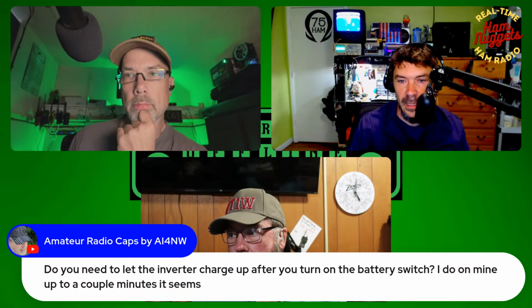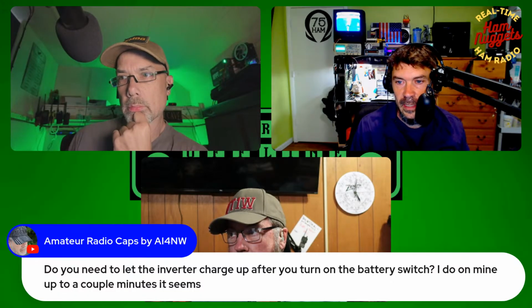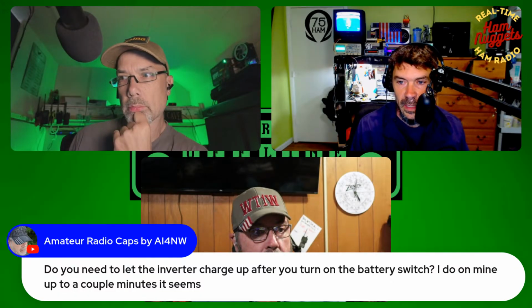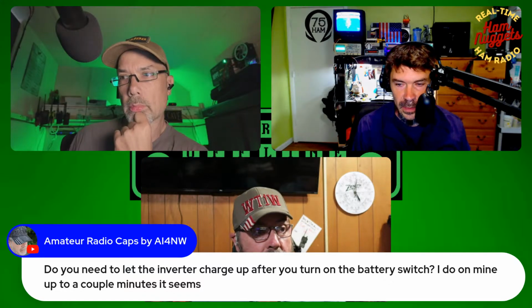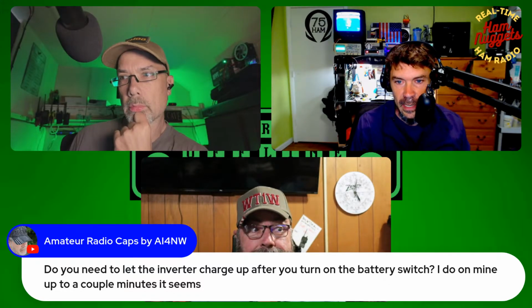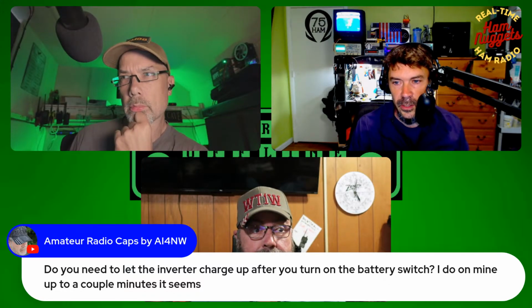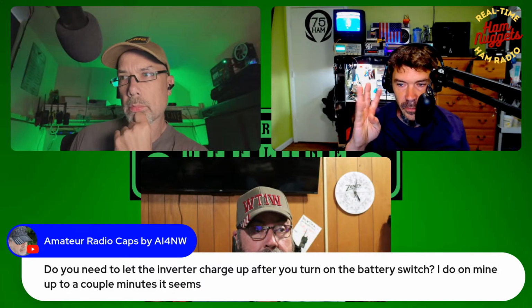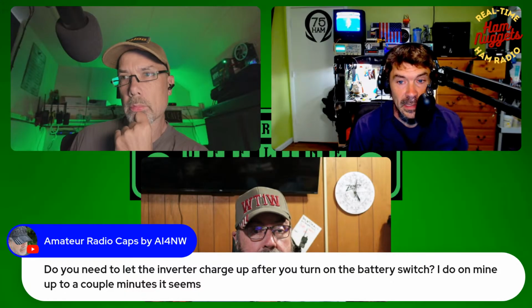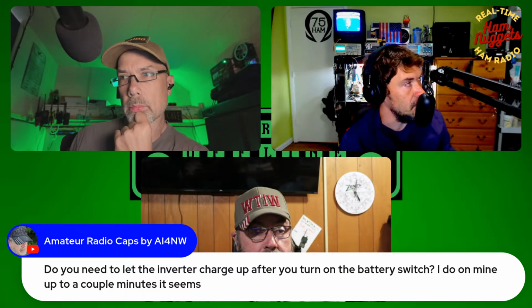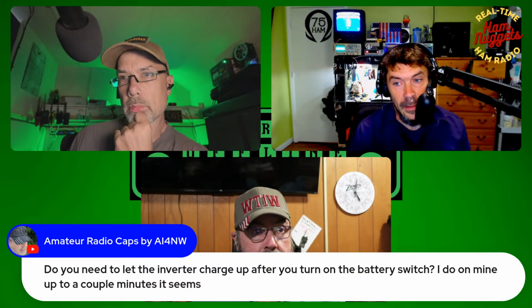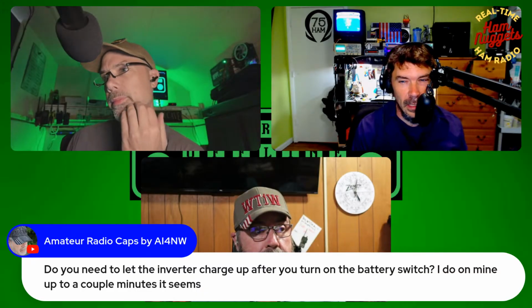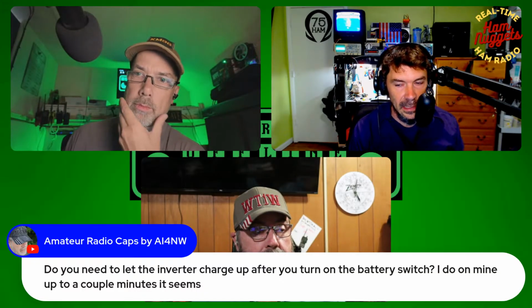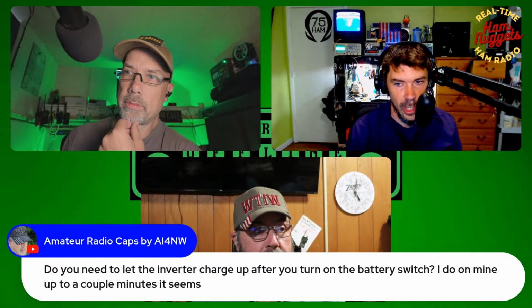Don's talking about them being bad for RFI because they're often installed badly. Well, it wouldn't actually matter how they're installed, because they're natively grounded. All the extra grounding is just redundant. It's actually a 4-conductor cable, and they're all bonded. I'm not saying they're not noisy, but I don't think you could install them badly. They're either just going to be noisy on your property or not.